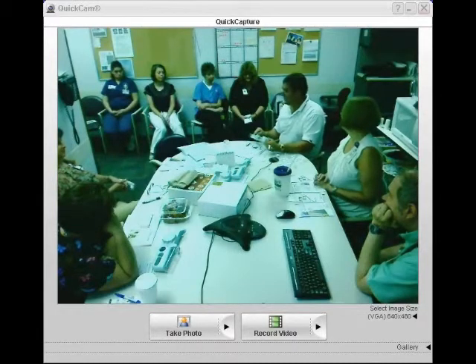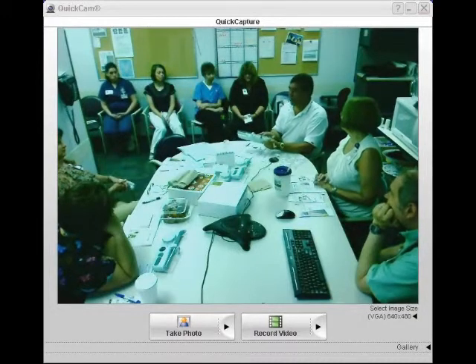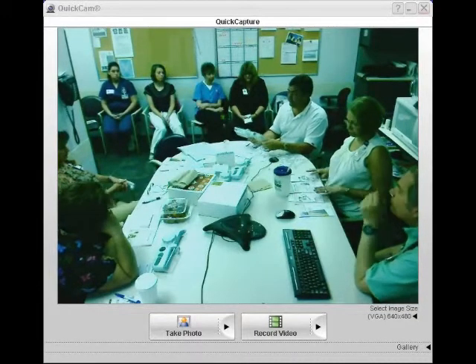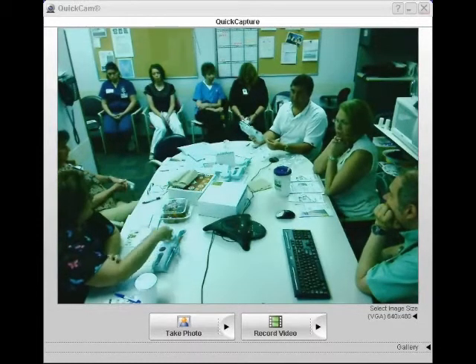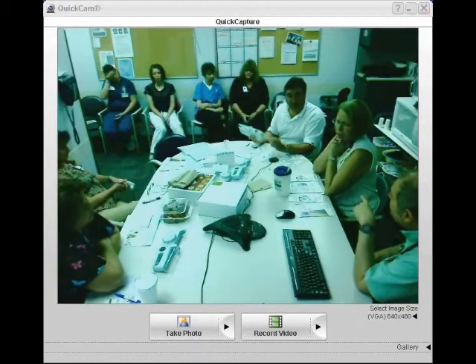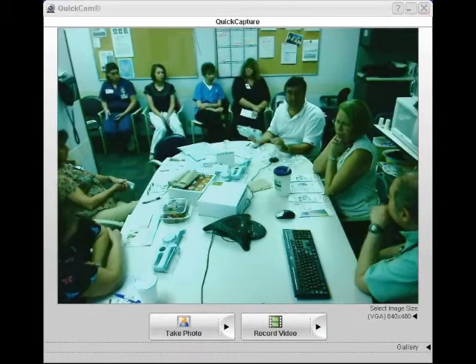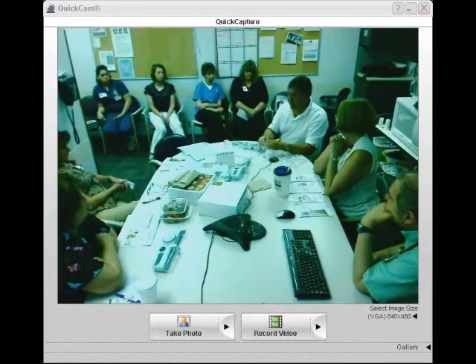As I do that, that drives this little black mechanism towards the syringe, pushes at. It's still pushing, but you can see how quiet it is. That's what the sound is when you have product in there. So if I fill this with water... So it's on right now? So it's on right now. Just the initial part till the syringe driver gets in place is noisy, and then once it hits the product, it puts a certain amount of pressure on it, and then the pressure regulator controls how fast it flows through. So that's how it works.